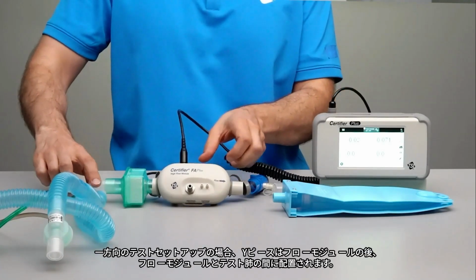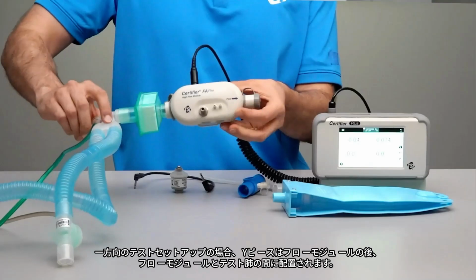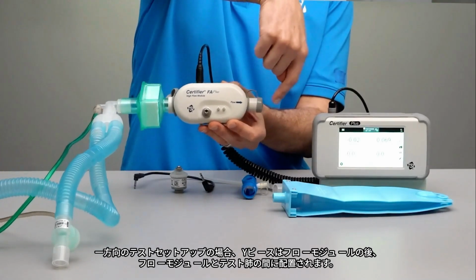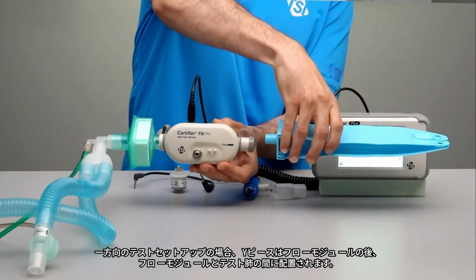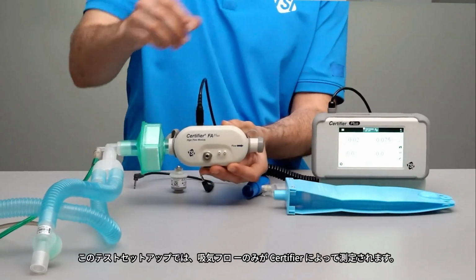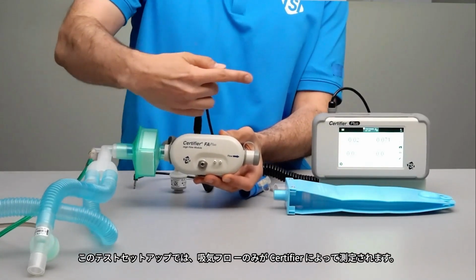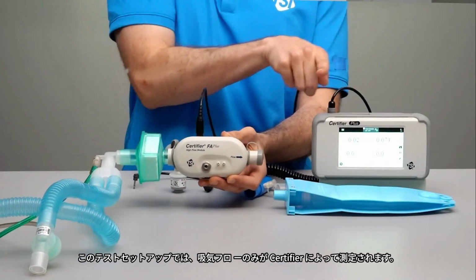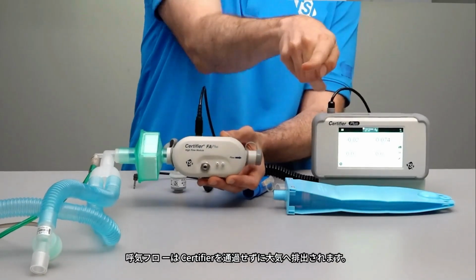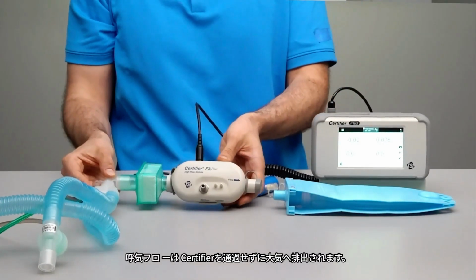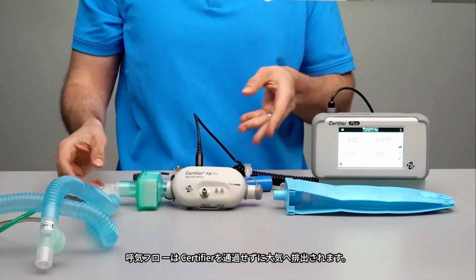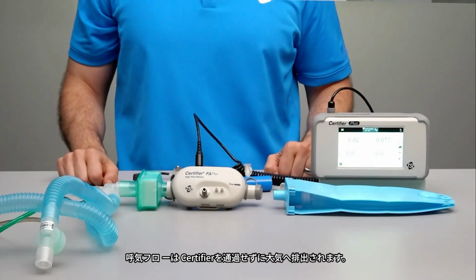For a unidirectional test setup, this Y fitting would be placed after the flow module, between the flow module and the test lung. With this test setup, only the inspiratory flows would be measured by the certifier, and the expiratory flows would be diverted from passing through the certifier instead and would vent to the atmosphere.